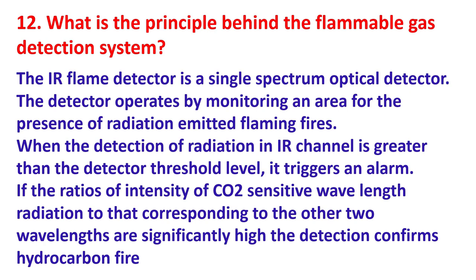What is the principle behind the flammable gas detection system? The IR flame detector is a single-spectrum optical detector. It operates by monitoring an area for the presence of radiation emitted by flaming fires. When the detected radiation in an IR channel is greater than the detector threshold level, and the ratio of intensity of CO2-sensitive wavelength radiation to that of the other two wavelengths is significantly high, the detection confirms a hydrocarbon fire.